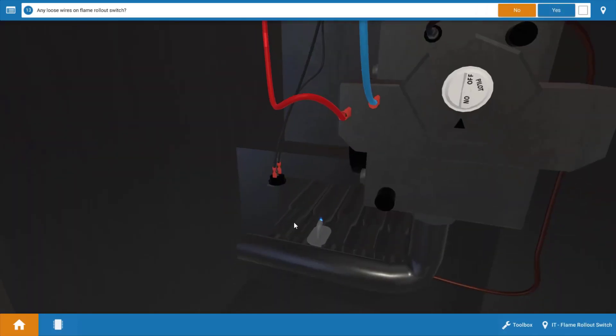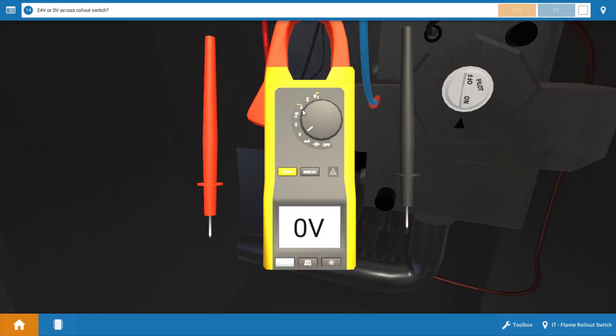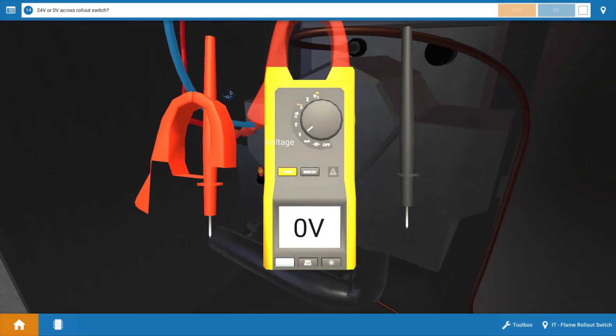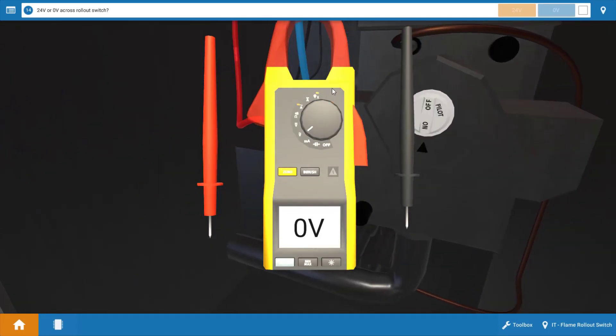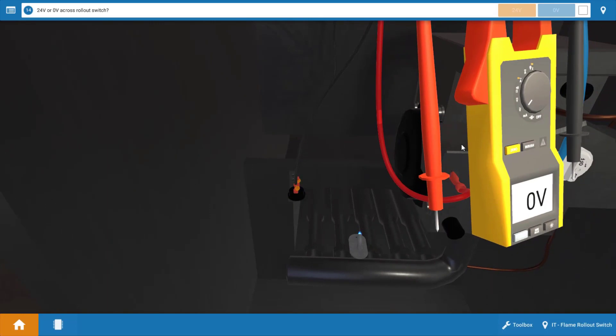Next, we're going to go to the flame rollout switch. Now here's the flame rollout switch down here. You can zoom in to get a better look at it and just make sure there's no loose connections, and you can see the connections are very secure here. Now the rollout switch really protects against delayed ignitions within the boiler, and this is usually due to either dirty burners that result in a delayed ignition and a flame rollout of the front of the boiler, or it could possibly be due to a competing exhaust appliance nearby that's pulling the flames out the front of the boiler. And this is just a temperature-actuated safety switch that when the temperature is too hot there, it's going to trip and turn the gas valve off.